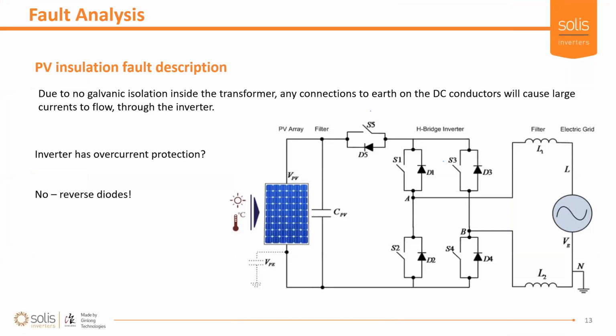Our inverters don't have a large, heavy transformer inside of them. A transformer is a device that converts AC voltage from high voltage to low voltage, but the main advantage that you get from it is galvanic isolation between the DC, your solar panels, and your AC. Our inverters don't have a transformer, so there is no isolation between your solar panels and your AC grid. Transformers in PV inverters like this are not worth it. You lose efficiency. The inverter becomes extremely heavy, and there is really no need for it. It works perfectly without a transformer.